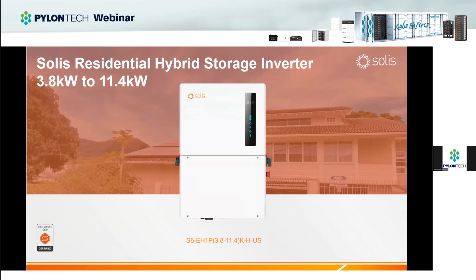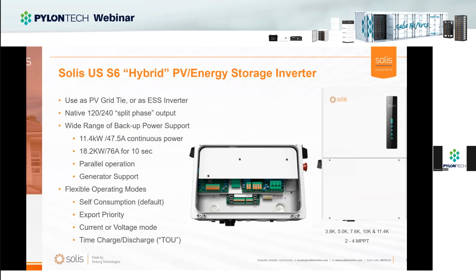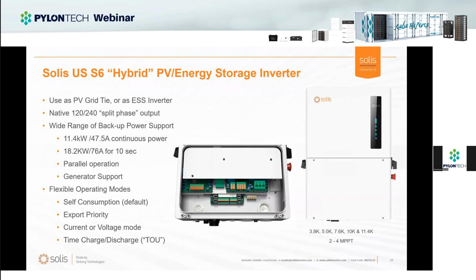The hybrid, we're very excited about. It's really just a grid tie inverter that's battery ready, and it has native 120-240 split phase. That's an improvement over our last product, which needed a separate piece. This one is just literally line one, line two, neutral, and ground over to your breaker box for tie into the grid. Should you want a backup panel for a partial home solution, you can tie to the backup panel, and you'll get that Pylontech power within 10 milliseconds—you won't even know the power went out for whatever loads are in that critical loads box.